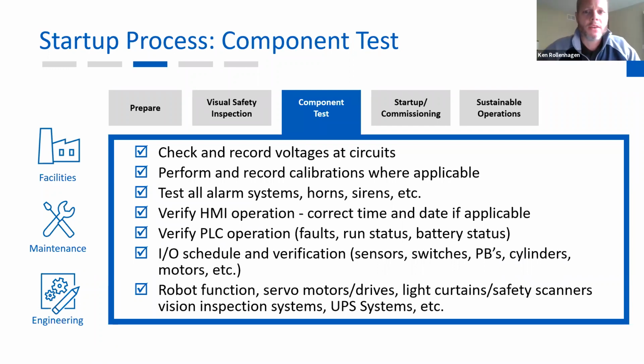All right, so when it comes down to a component test, we've energized the machine, we've already performed our visual safety inspection, so we're going to energize and go through a very thorough checklist to bring things online. Whether this is the facilities, the one-line diagram, our main feeder panels down to our plant level, we want to take some voltage readings, right? We want to document those. We can use those to cross-compare in years following. That'll be a leading indicator for our transformers, things like that. We want to record any calibrations where applicable, making sure if a device or component has a calibration, we know the requirements: when does it need to be tested and recalibrated?